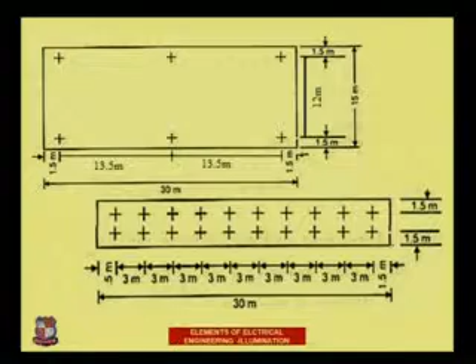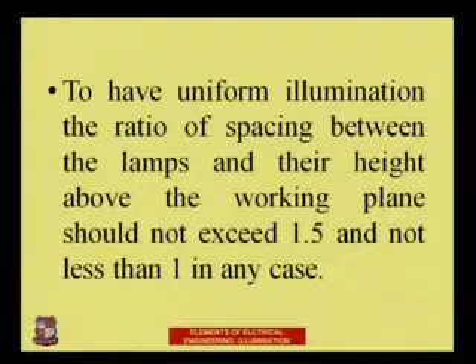To have uniform illumination, the ratio of the space between the lamps to the height above the working plane should not exceed 1.5 and should not be less than 1. That means it is giving you a proper range between 1 and 1.5, which should be kept in mind whenever you are designing any type of light fitting.